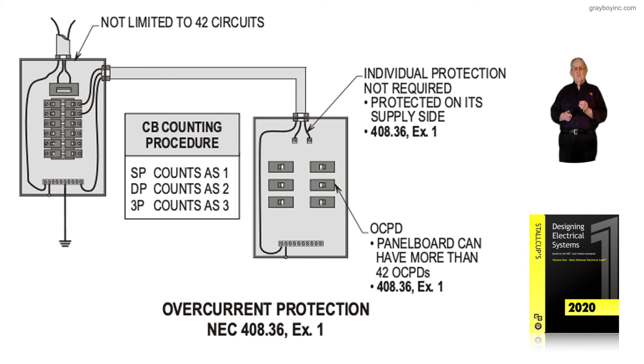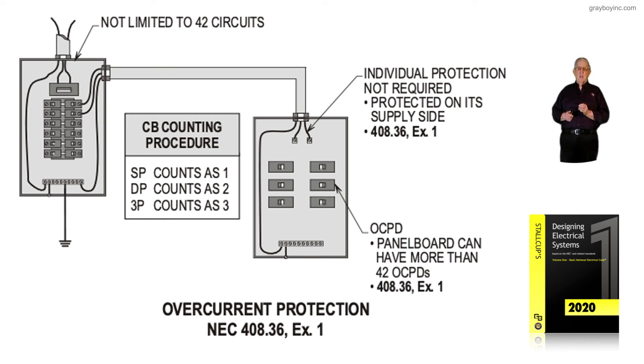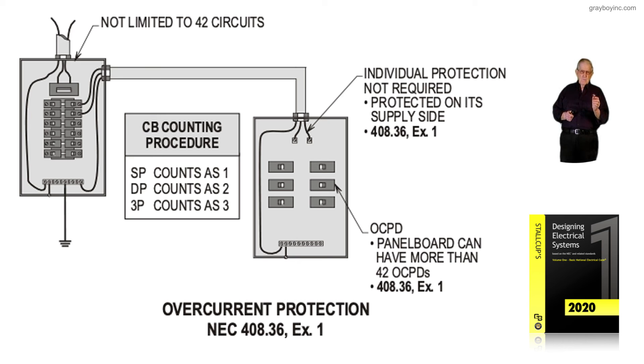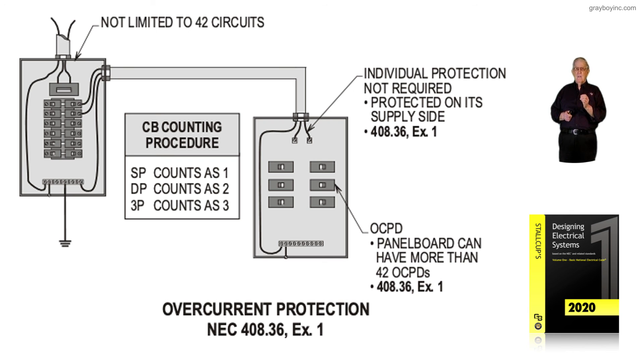It's not an industrial or single-management-type facility. We covered that if you've gone through this presentation and picked up Chapter 6 — just go to Chapter 6 to review in more detail where you feed from one building to another. Figure 7-15 shows that the subpanel does not have an overcurrent device, and you're not limited to the 42-circuit rules when 408.55 is applied, illustrating how Exception 1 to 408.36 applies in relationship to where overcurrent protection mains are required.